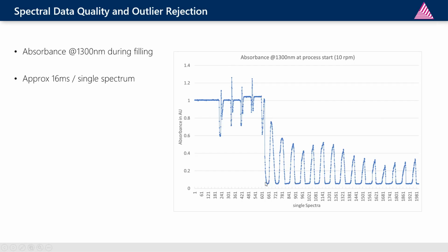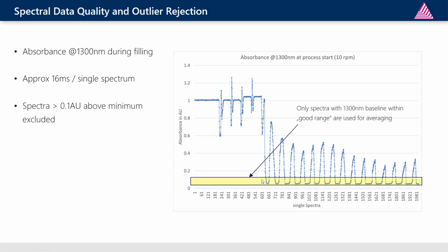This is a good example of how the outlier algorithm is working. A single measurement is really very fast. Every blue dot is a single spectrum taken. The rejection algorithm just rejects everything which has a too high baseline, because high baseline means bad sample presentation. In this case, it's usually the distance of the powder bed between the window of the probe and the surface of the powder, which in our case was not constantly connected to powder. But with this outlier rejection algorithm, we can remove all the non-well presented spectra quite efficiently.